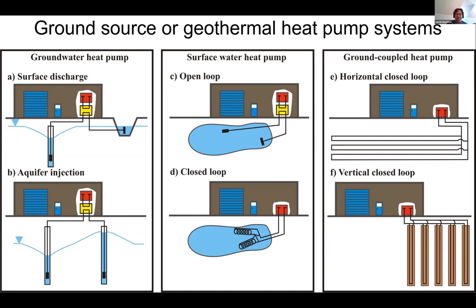Risk of clogging the wells, having aquifers that are not permeable enough, or scaling and corrosion of the plate heat exchangers, because in those systems, you never send the water directly into the heat pump. That's what I show on my graph here. The yellow box is an intermediate plate heat exchanger that allows transferring the energy from the ground to the heat pump, the red box, and then to the building. So the open loop systems are a little bit more risky, but more performant, while the closed loop systems at the other end are less risky, but tend to be a little bit more expensive.